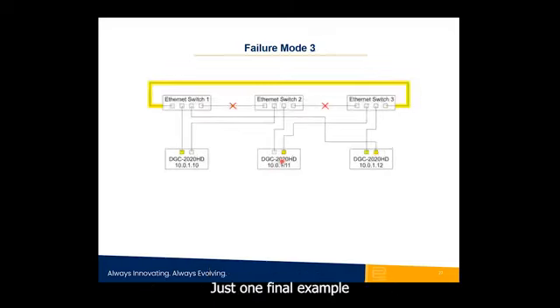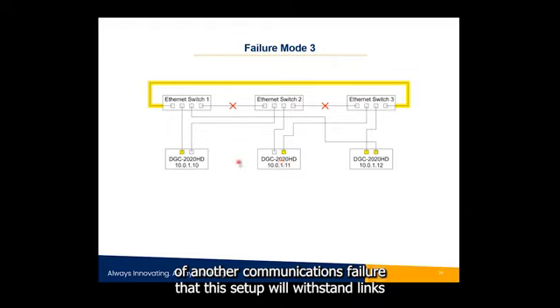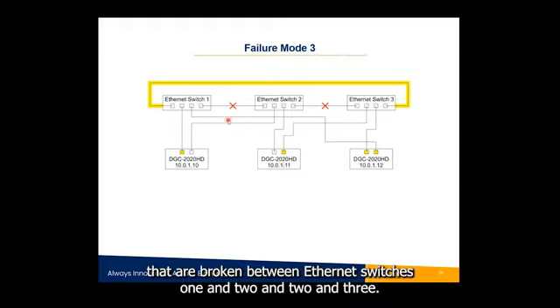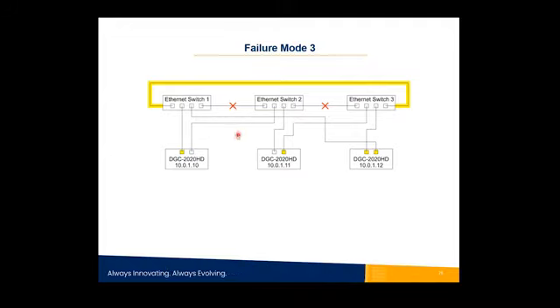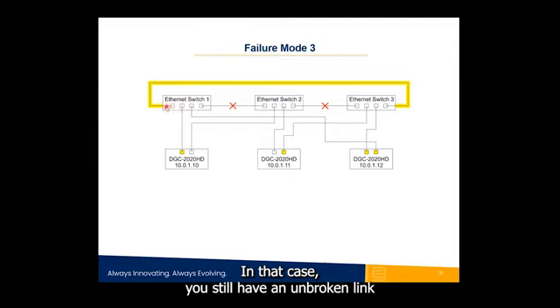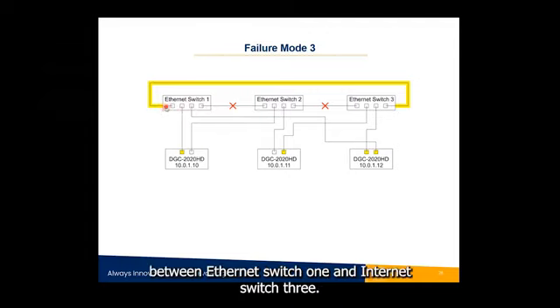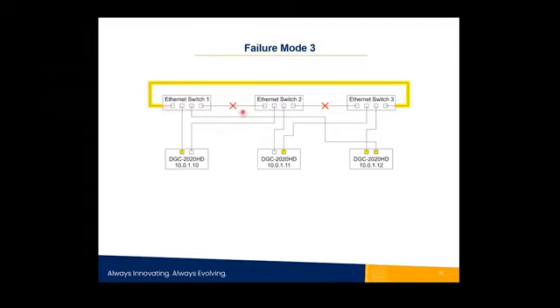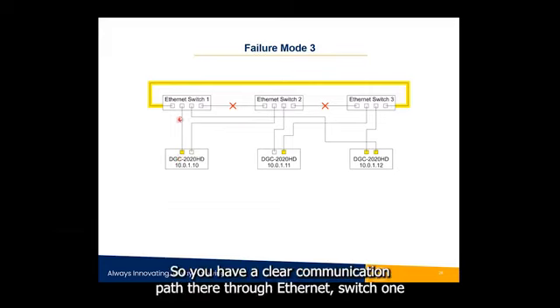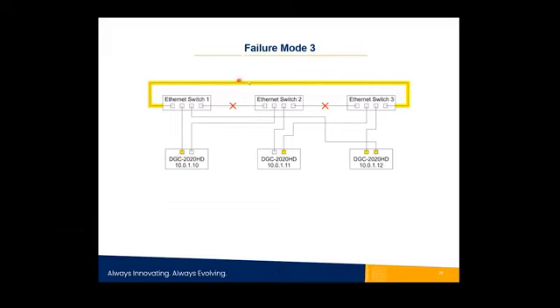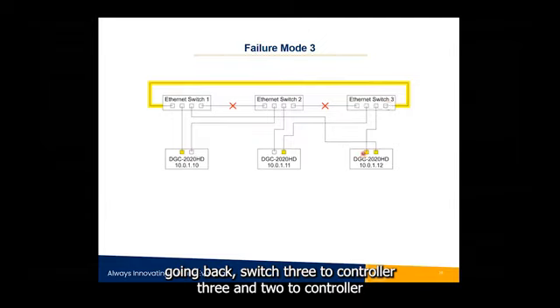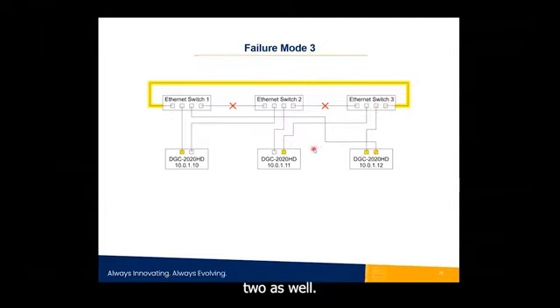Just one final example of another communications failure that this setup will withstand: links that are broken between Ethernet switches 1 and 2 and 2 and 3. In that case, you still have an unbroken link between Ethernet switch 1 and Ethernet switch 3. So you have a clear communication path here through Ethernet switch 1, going back through 3 to controller 3 and to controller 2 as well.